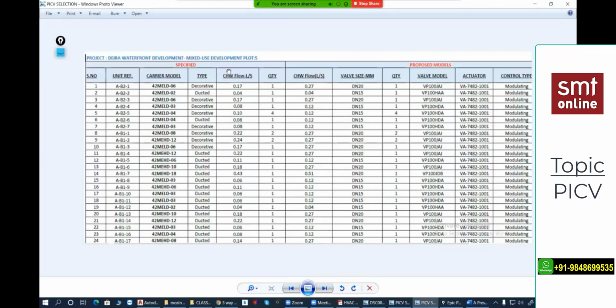But now you see, from the PICV manufacturer, the available is 0.27, and they provide the size, 20 mm, quantity, then the valve model, actuator model, and controlling. Sorry, I missed it. Apart from this, they will provide one more piece of information which is missing in this image: the valve position. Yes, valve position. That is a requirement. You see, this is our requirement, and we got this one.